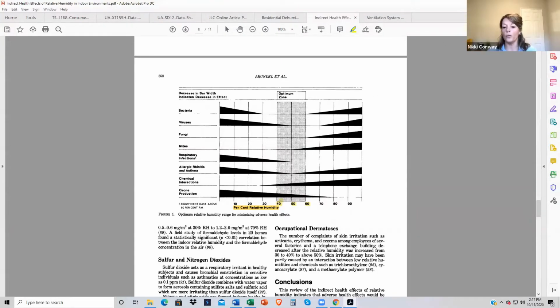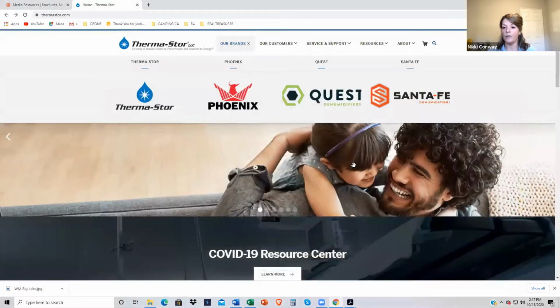Typically if you have a basement in the Midwest or Northeast, we'd start with dedicated dehumidification in the basement. Basements typically have a lot more moisture - they're cooler, which means relative humidity is higher. That's why in the industry we really want to make sure we understand dew point.